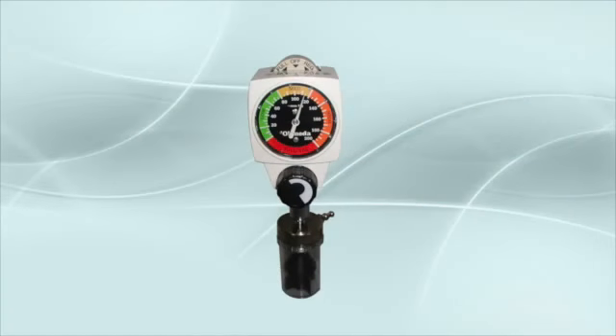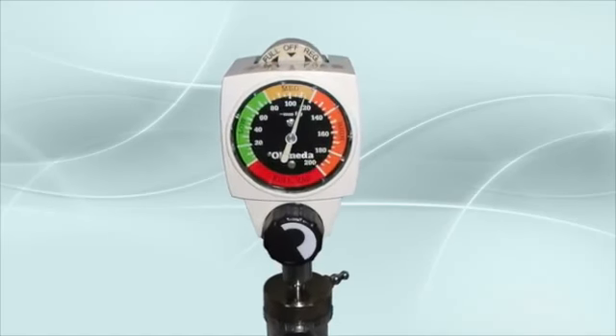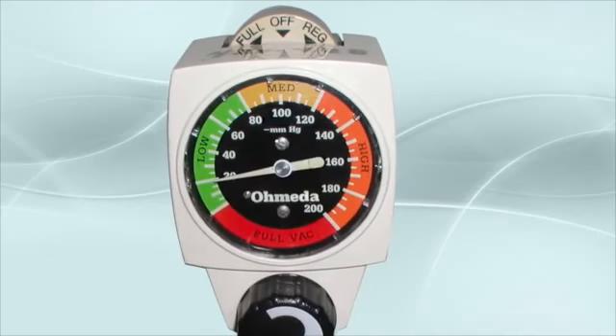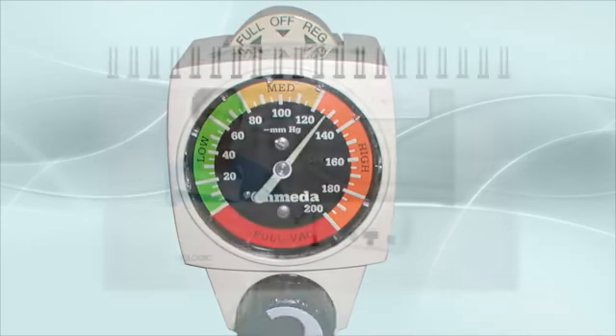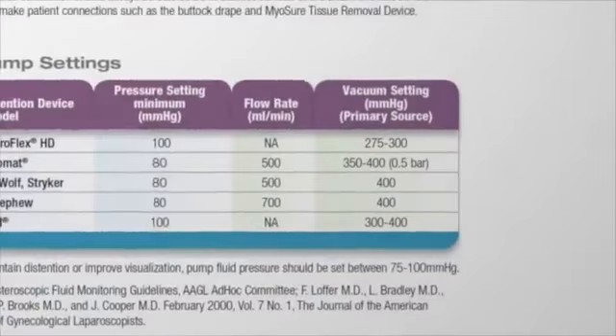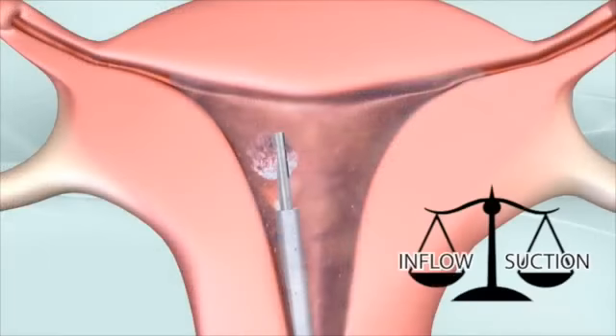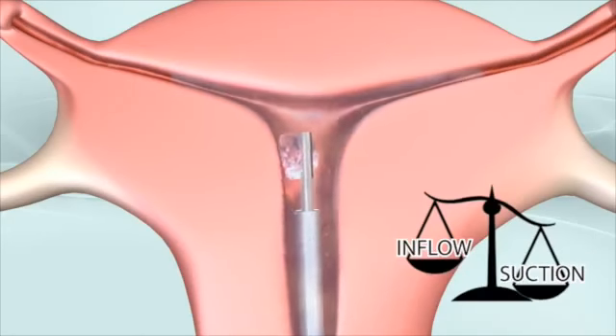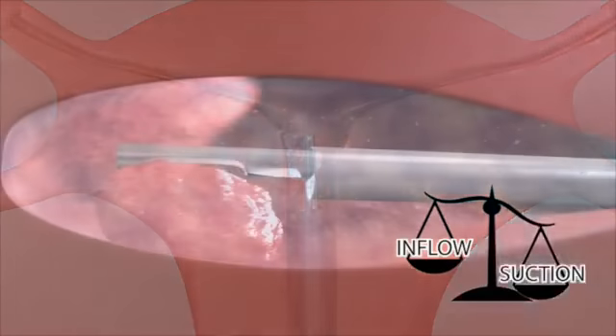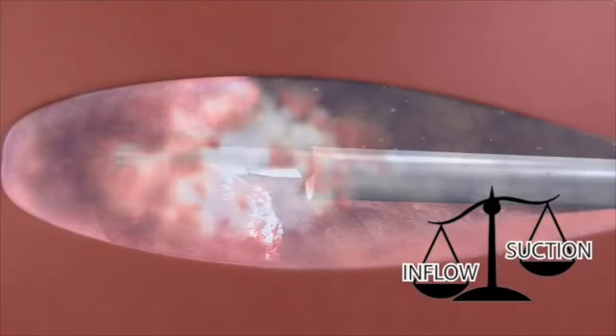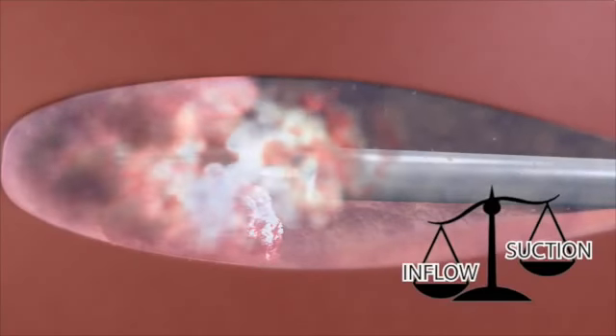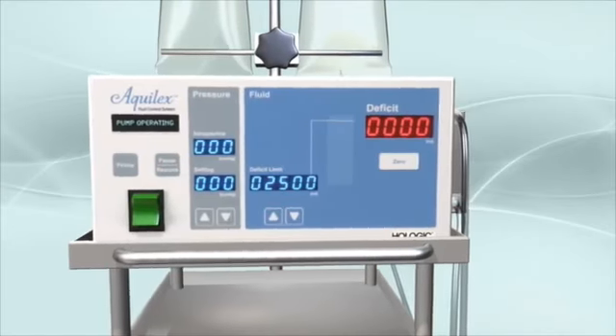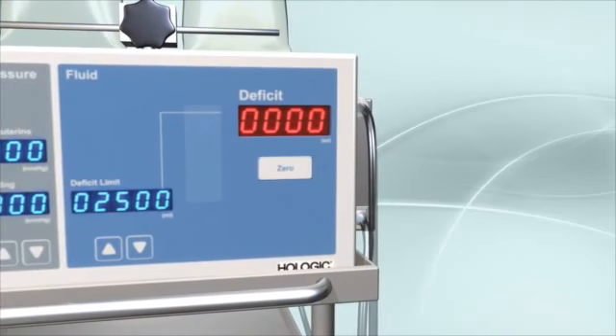Each fluid pump performs differently, and therefore an adjustable suction source should be used during the Myosure procedure to provide vacuum pressure adjustments based on the inflow performance of the fluid pump used. It is important to set the vacuum pressure based on the recommendations in the Myosure setup guide. The vacuum pressure significantly affects uterine distension and cutting efficiency. If the vacuum is set too high, distension will deteriorate quickly when Myosure is activated. If set too low, obscuring tissue may not be evacuated at the desired rate, and venous absorption of fluid may become an issue. It is important that the physician and staff monitor fluid deficit volume throughout the procedure. In accordance with the ACOG guidelines, the procedure must be stopped if this value exceeds 2,500 cc's.